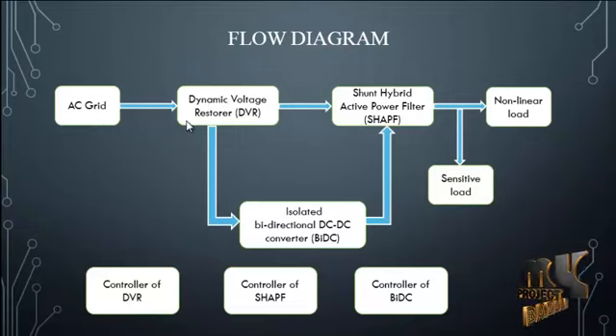The dynamic voltage restorer detects voltage swell and voltage sag on every phase and every line, and dynamically restores each line through specific charging and settings that are automatically processed. So we use the dynamic voltage restorer for line injection.